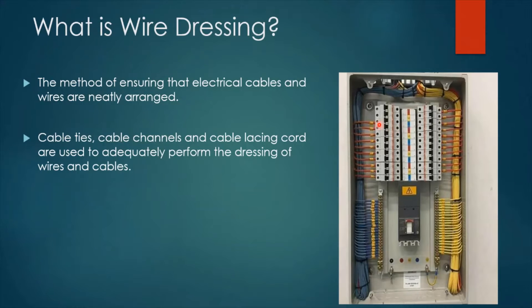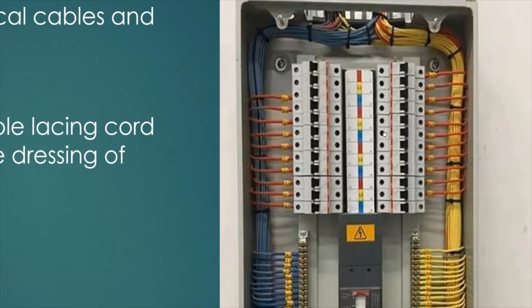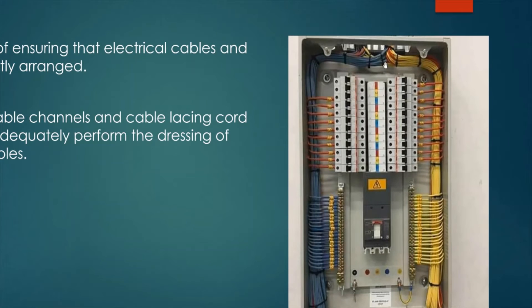Now let's look at what is meant by dressing, or wire dressing. It is the method of ensuring the electrical cables and wires are neatly arranged inside the distribution board enclosure. In order to do the dressing in a proper way, cable ties, cable channels, and cable lacing cord are used. As we can see in this picture, the wires are neatly arranged inside the enclosure and also neatly terminated inside the circuit breakers of this DB.